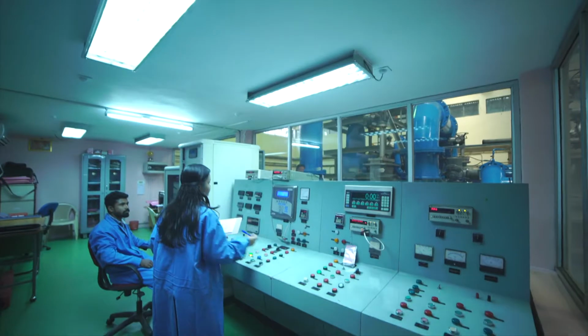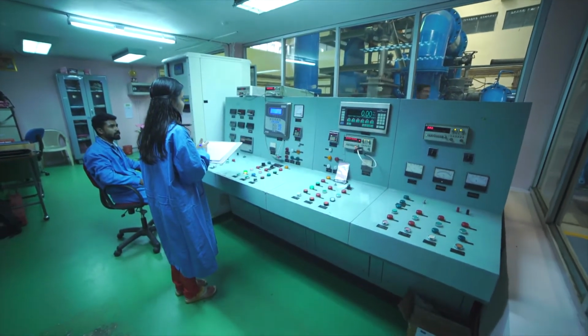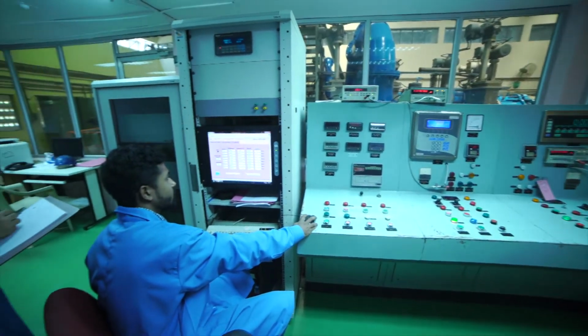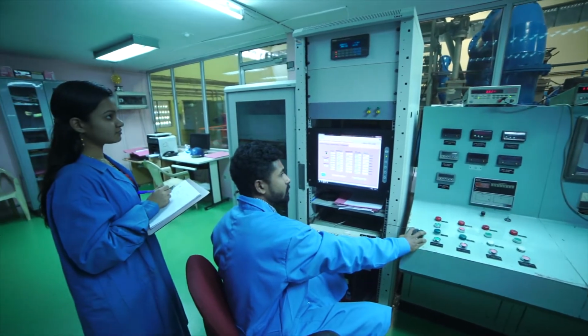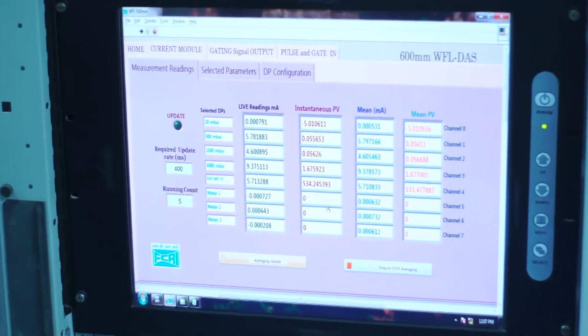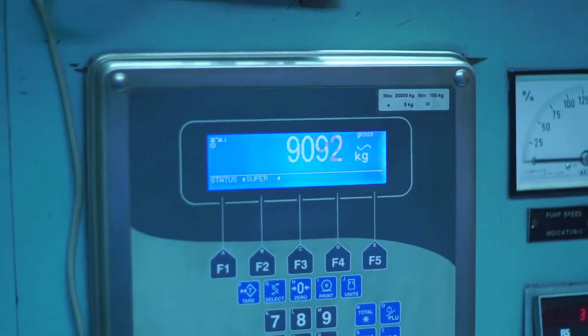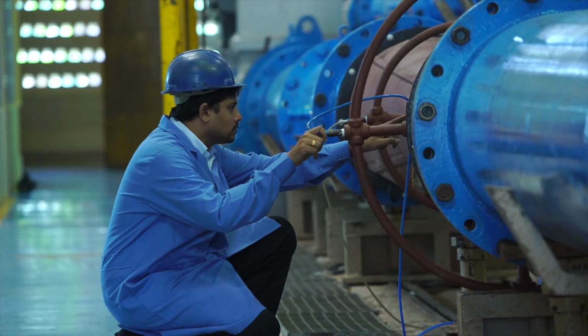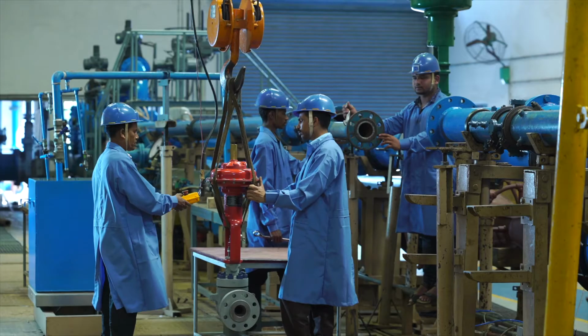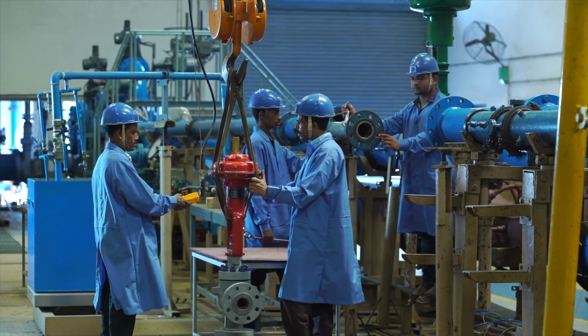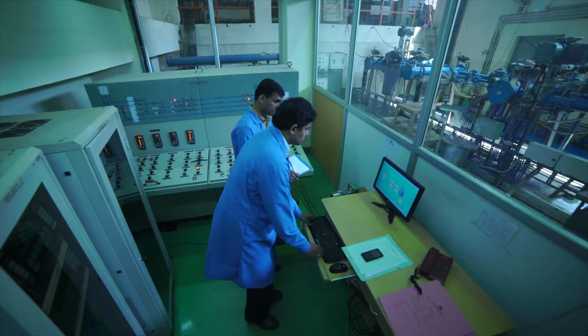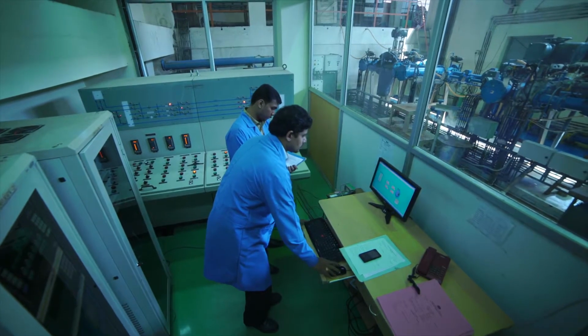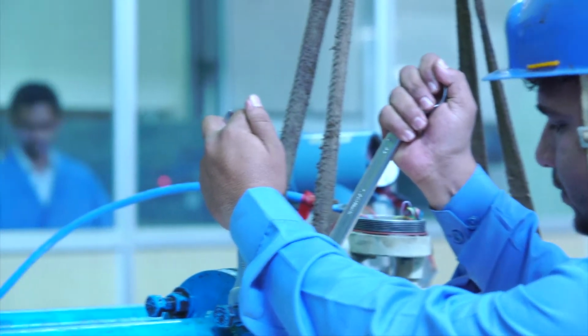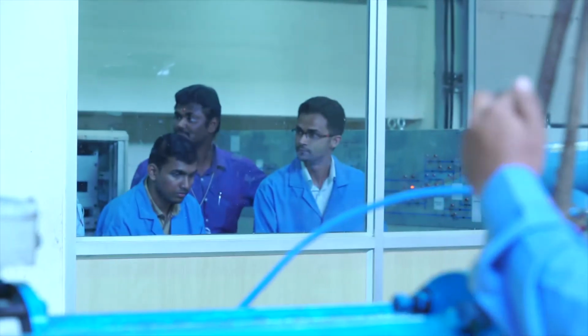All types of flow meters, including differential pressure, electromagnetic, ultrasonic, and Coriolis mass flow meters, are evaluated here with the highest accuracy level. Flow products of up to 900 mm diameter can be evaluated in this facility. Testing of control valves is one of the major activities of the laboratory.